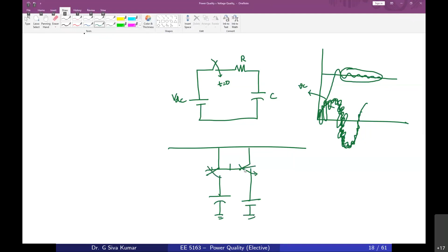At that moment, there is a sudden variation in the energy levels, sudden changes in the energy levels, that results in an oscillatory transient current in tens of kilohertz, as illustrated in this figure. This is a typical oscillatory transient current caused by back-to-back capacitor energization. You can see that the charging current it takes is something around 7,500 amperes. After a duration of 5 milliseconds, the current decays once it has been charged to the rated value.